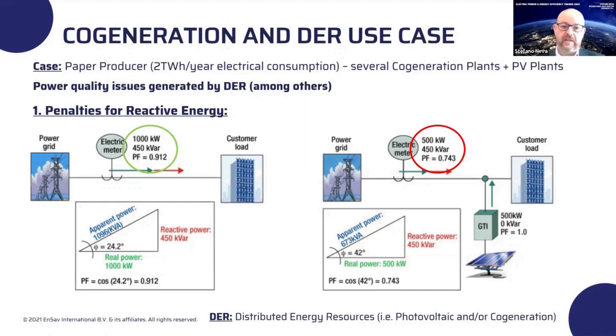But this creates the fact that the same amount of reactive energy will be counted by the utility meter, and because they are taking less energy from the grid, this will change the ratio between active and reactive energy, and their overall power factor will drop below the penalty level. They are paying something like 130,000 euros every year as a penalty.